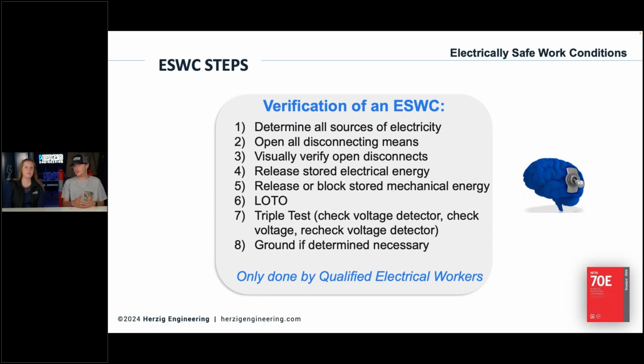All things are considered energized until verified de-energized through this 8-step process. That note is important: it's only done by qualified electrical workers. If you can get to that de-energized point, the chance of human error for electrical hazards hurting or killing somebody drastically drops.